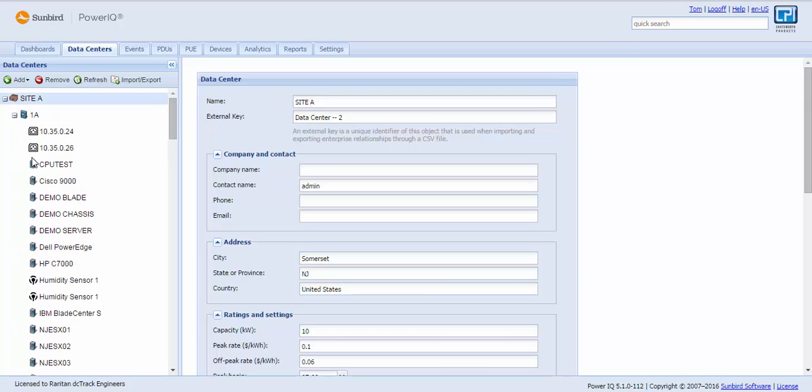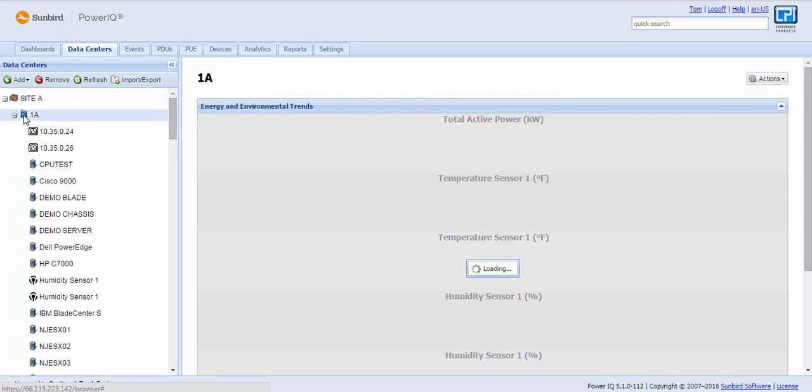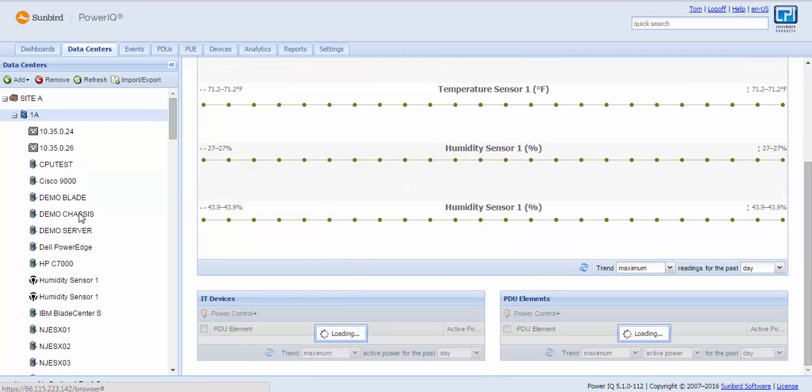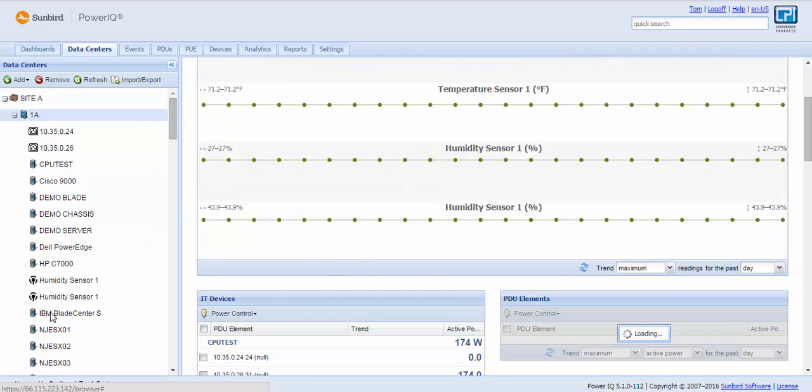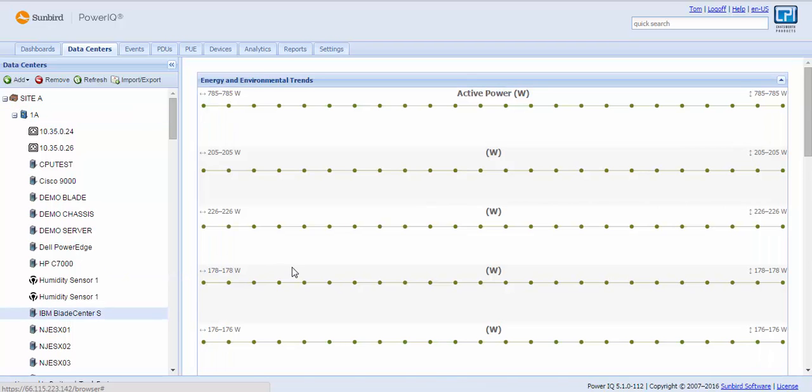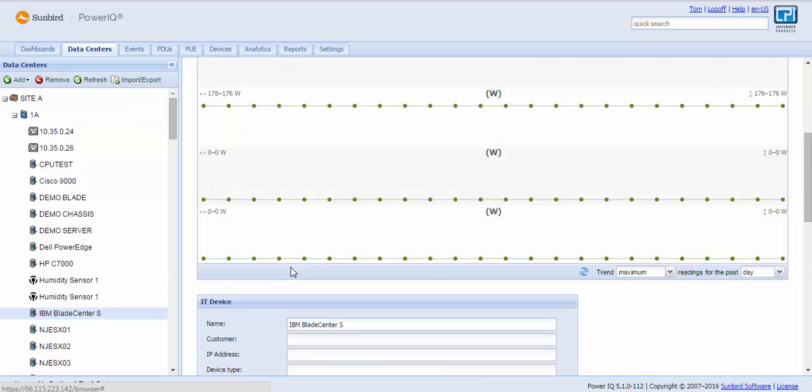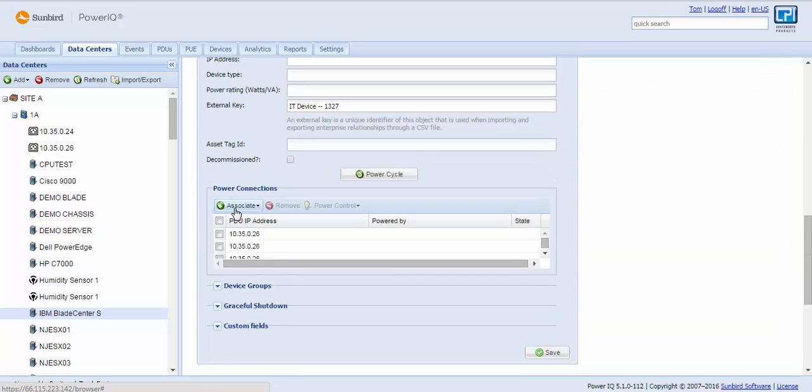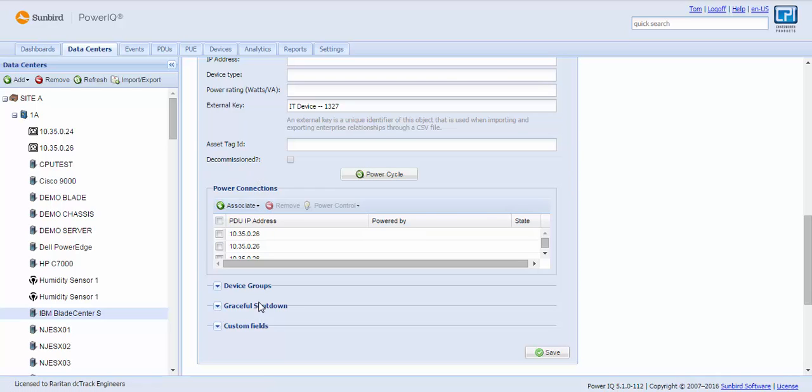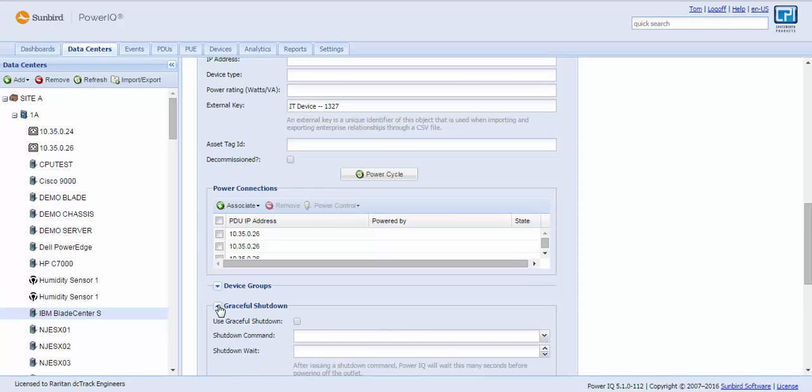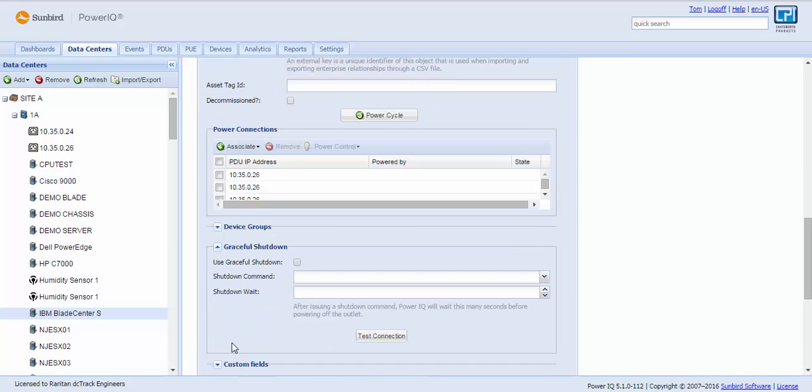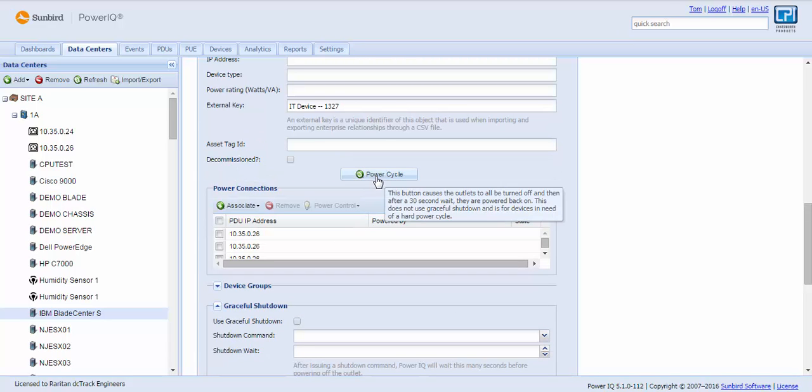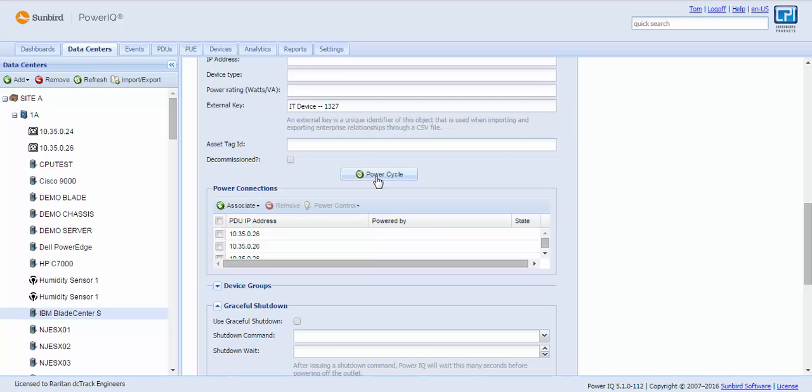Navigating the data center hierarchy is tremendously easy. I just click on rack one, and I get my smart charts for rack one, as well as my ability to look at an individual IT device and see smart charts for the load of the IT device over time, as well as the outlet or circuit association with this IT device. This can be put into device groups. We have a patent for graceful shutdown, so you can have a shutdown command entered, and when you cycle the power on this device, you can choose to go through graceful OS shutdown or a hard shutdown to just cycle the outlets. Power control is made easy. It's optional if it's enabled. You merely click a button to power cycle the device. We have configurable delays and sequencing for power control, as well as the ability to specify that an answer needs to be entered for why you want a power cycle, and those answers go into the audit log for full audit log tracking.